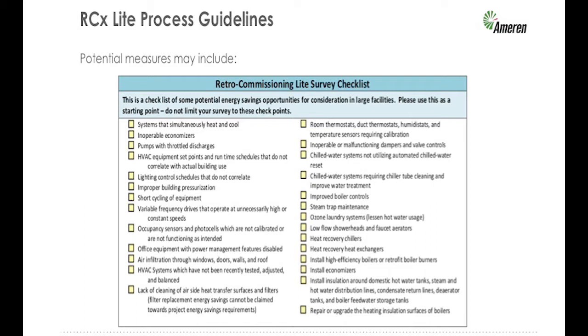With the RCx Lite and the large facilities program, these opportunities fall in the 0 to 1 year payback range — systems simultaneously heating and cooling, inoperable economizers, improved boiler controls, steam trap maintenance, and HVAC system controls adjusted and balanced, among others.